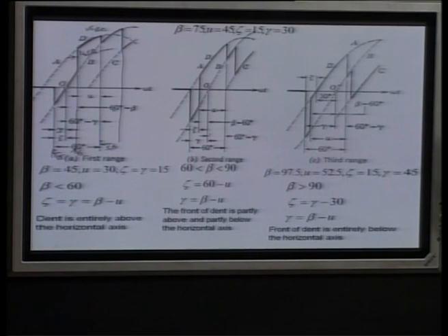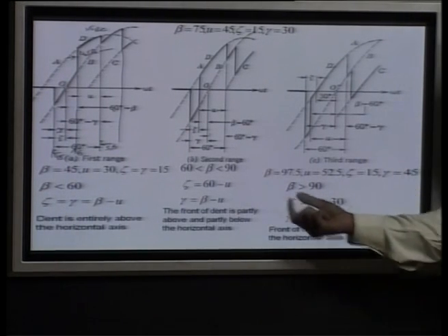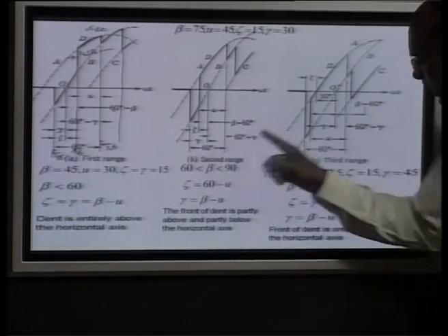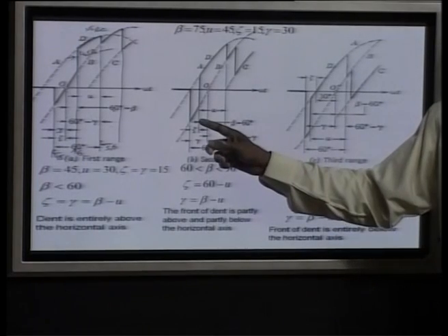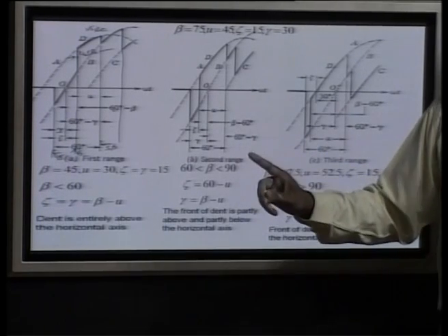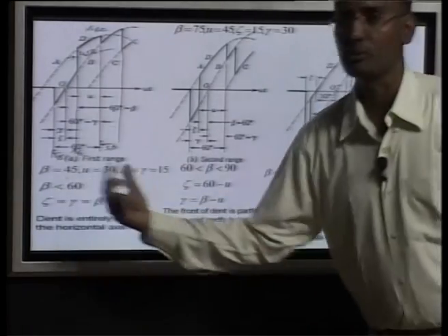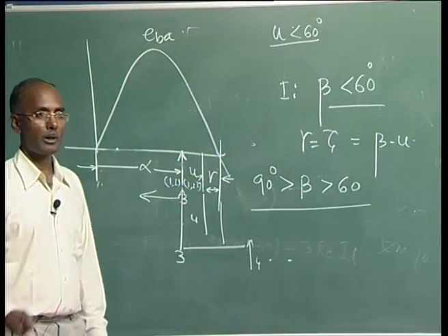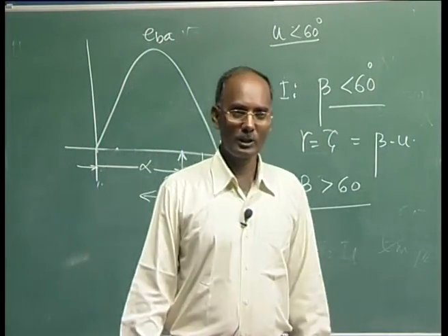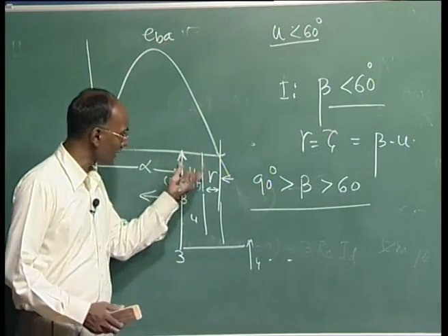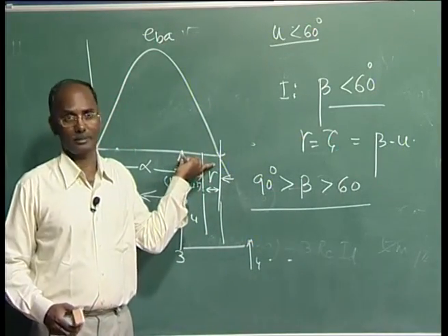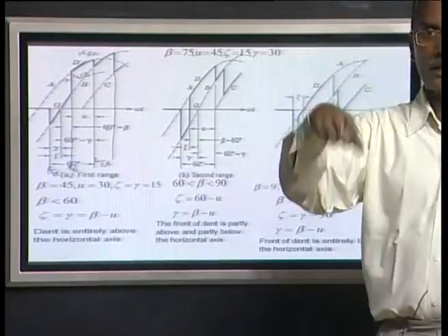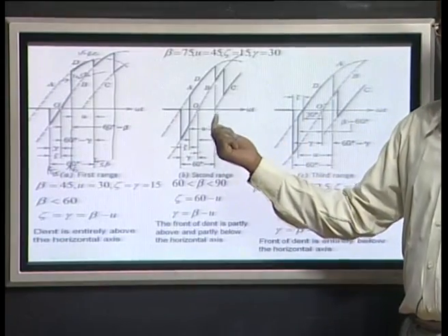So this zeta is very, very important, and if you are in this mode, you should be very, very cautious. But normally we operate our inverter in this mode. Why? If you come to this side, beta more, the power factor becomes very poor. We try to fire only at less than almost 30 degree, not more than that. But there is a possibility, due to fault etc., you can come to this side and commutation failure may occur.